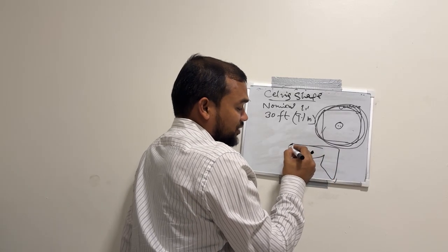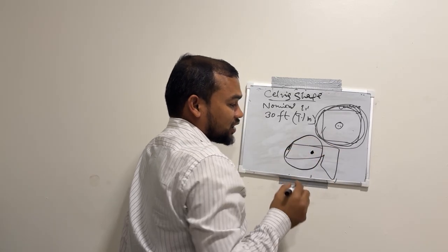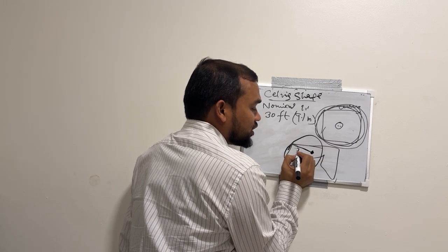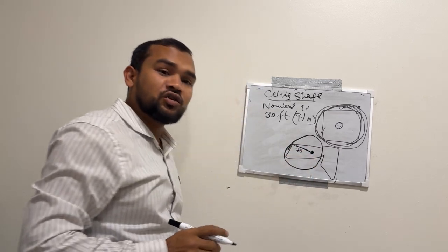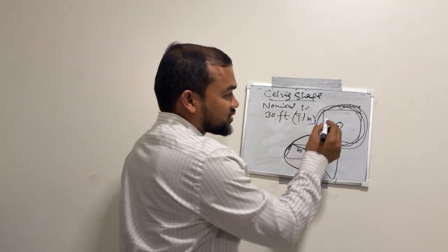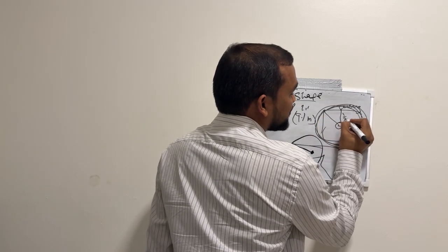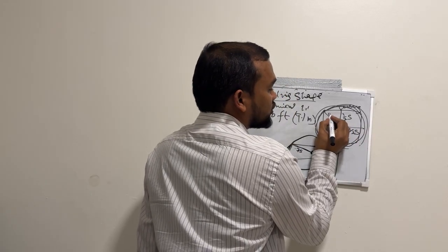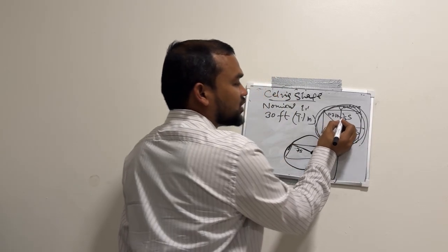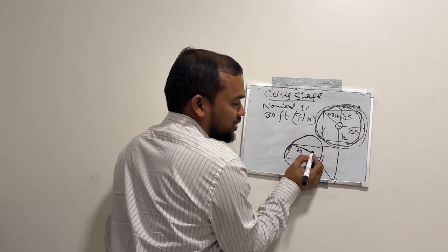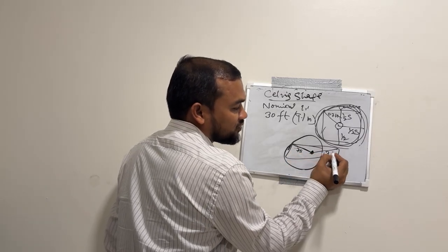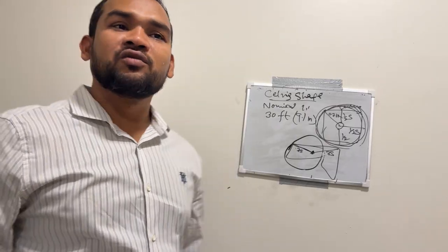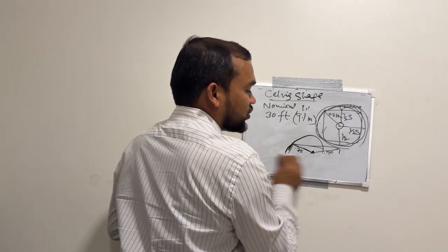It should be covered the same as in the nominal spacing, but for this irregular shape it should be 0.7 times the nominal spacing. So we always consider this half of the space, and this is 0.7 times the listed spacing. So we will always consider 0.7 times. So this is all we have to consider based on ceiling shape, irregular ceiling shape and normal ceiling shape.